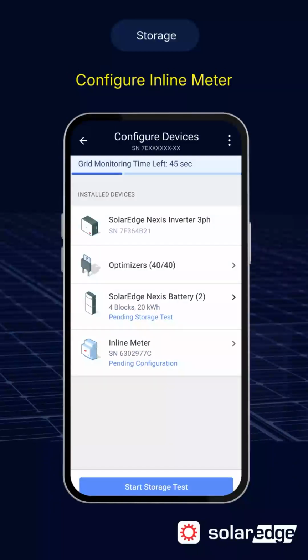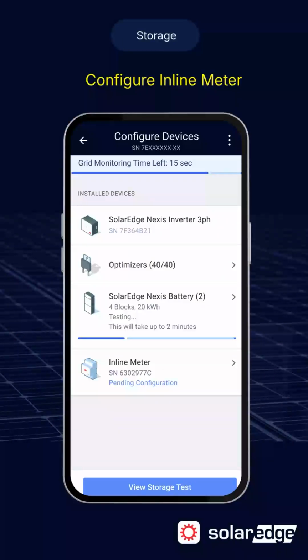Grid monitoring is now complete, and the storage test is in progress. SolarEdge Go is verifying battery communication, charging, discharging, and overall battery operation. You can monitor the test progress on screen while the test completes. The storage test is now complete. SolarEdge Go has successfully verified battery communication and operation. The system is now ready for the next commissioning step.